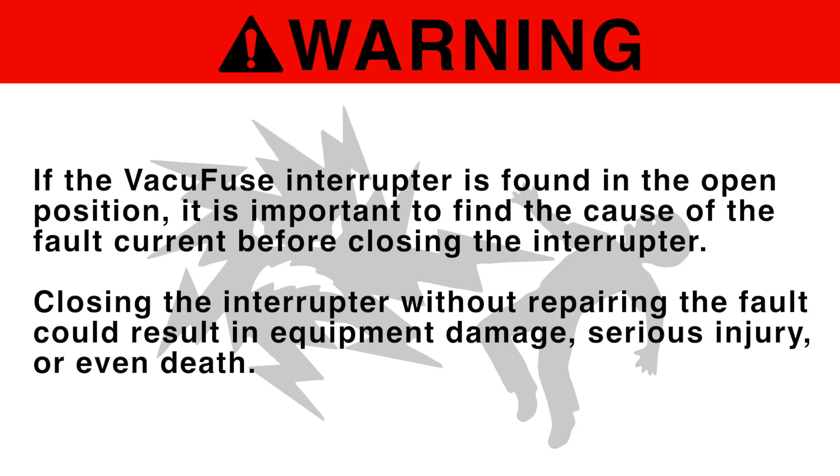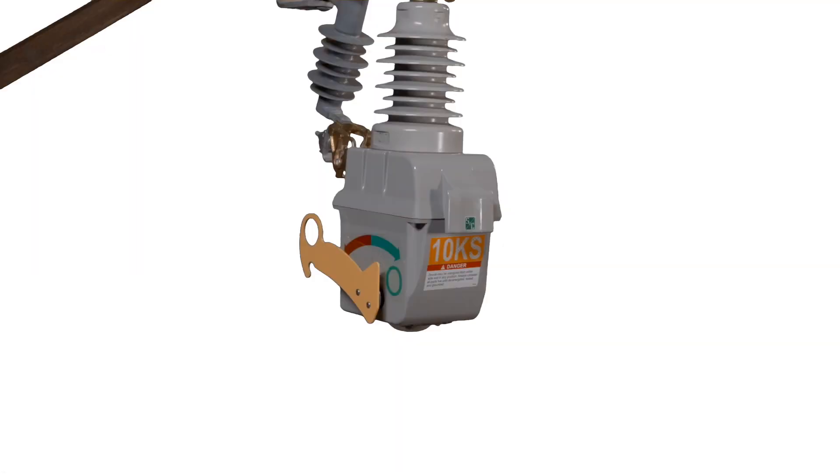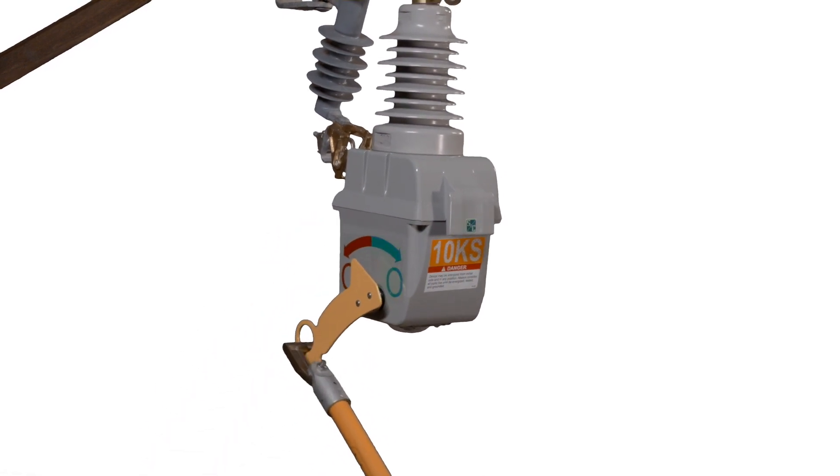If the VacuFuse interrupter is found in the open position, it is important to find the cause of the fault current before closing the interrupter. Closing the interrupter without repairing the fault could result in equipment damage, serious injury, or even death. After the cause of the fault has been determined and after any necessary repairs completed, the VacuFuse self-resetting interrupter can be closed by pulling down on the open-close lever.